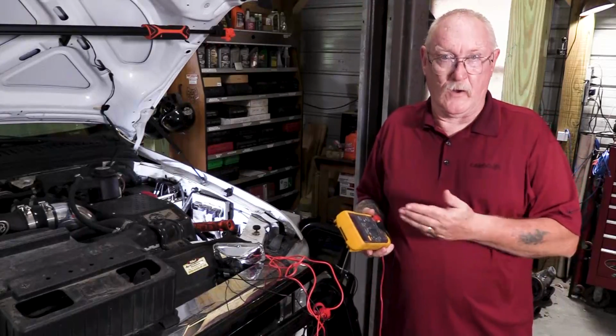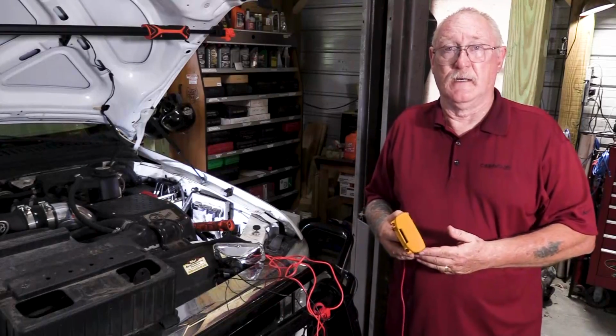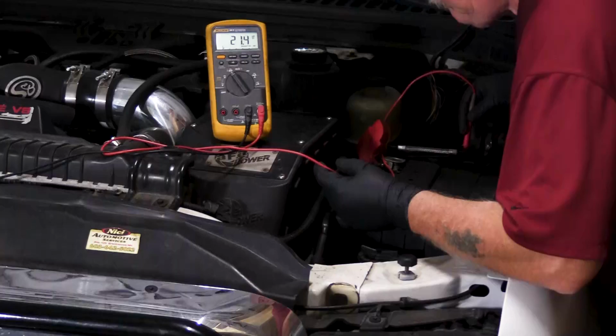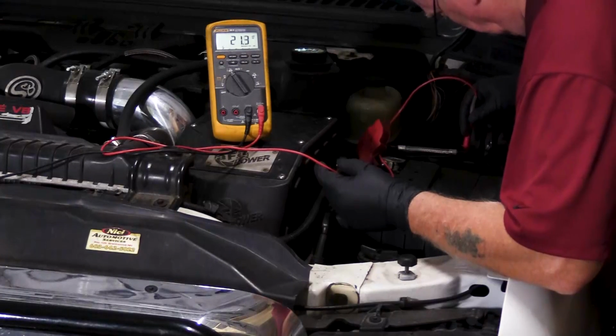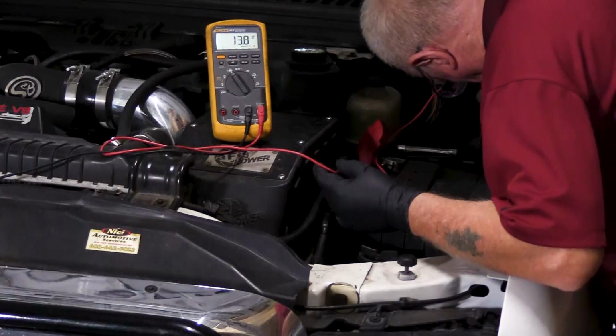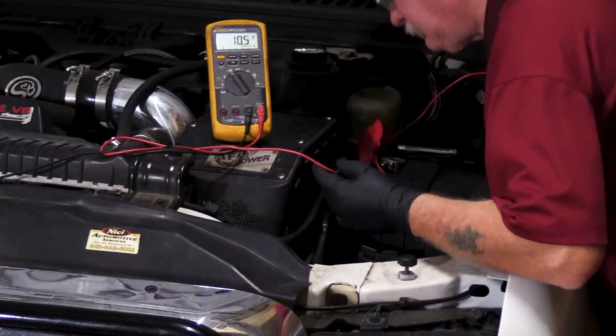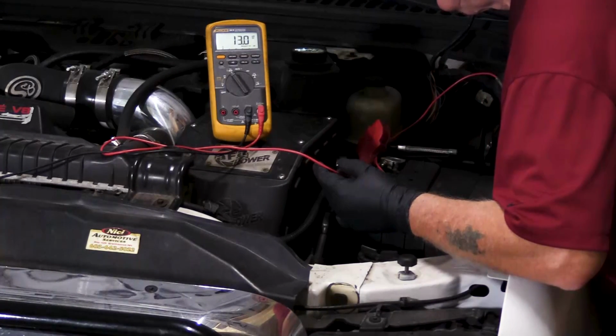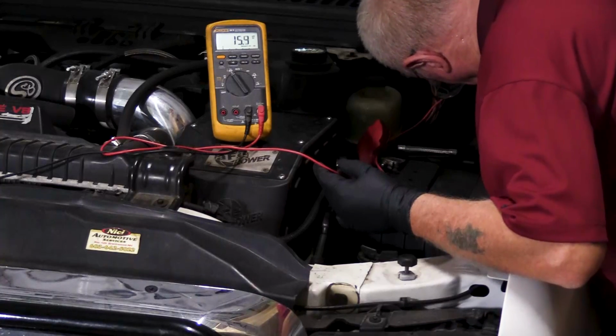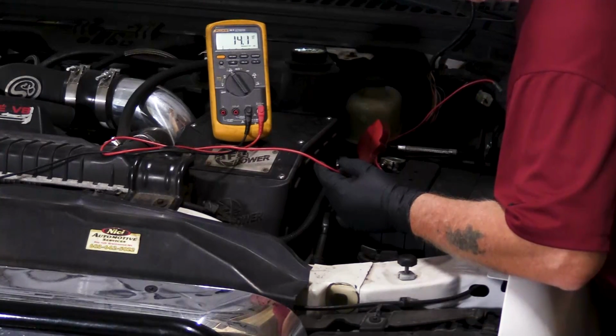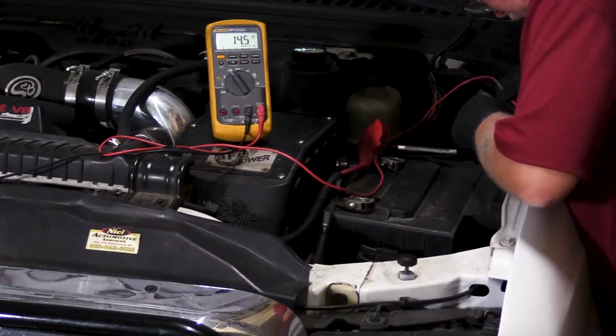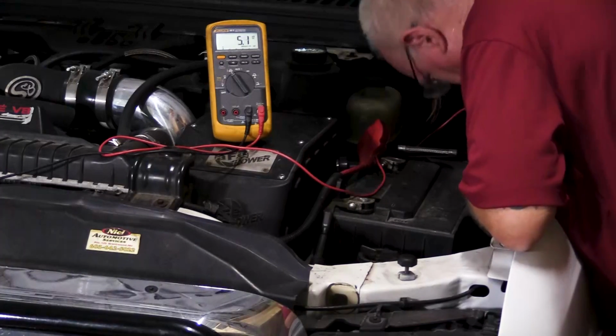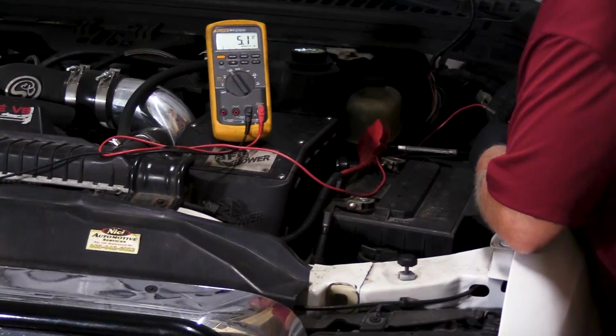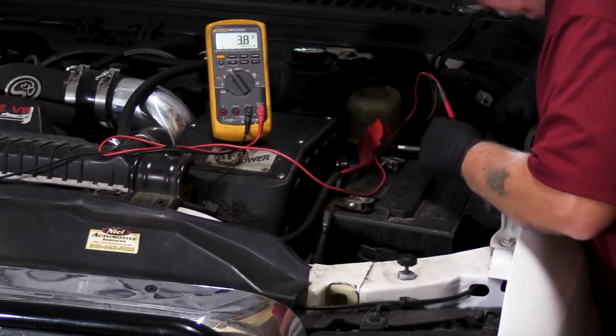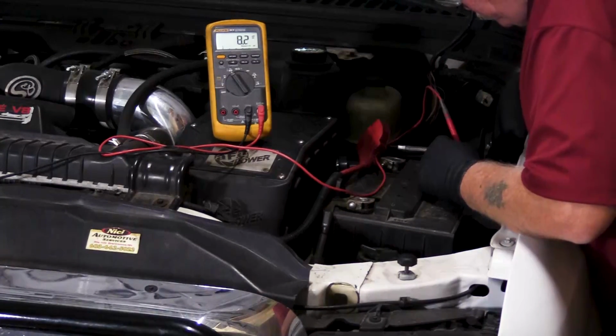And what if you do get an OL reading on the meter during one of your tests? How do you find the cause? Just like we learned in our last episode, work your way back to the battery using easy to access test points at first until the reading returns to normal. When that occurs, I know I've passed the problem and I need to head back the other way in smaller sections until the reading becomes bad again. The extra resistance that we're looking for lies between these two test points, and it's just a matter of continuing to narrow down the possibilities until the cause is isolated.